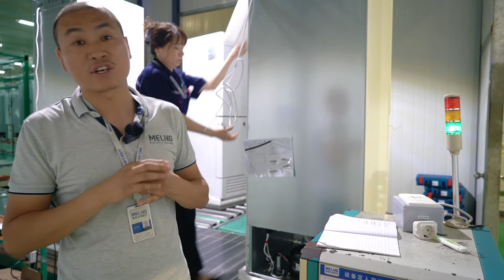After gas charging, the next step is the electrical safety test. If the cabinets pass through all these steps, we have an electrical safety tester to make sure electrical safety first. We normally take 4 items: the first is grounding, then the 1,800 voltage resistance, the electrical leakage, and lastly the isolation.